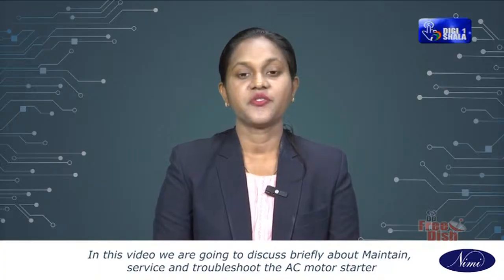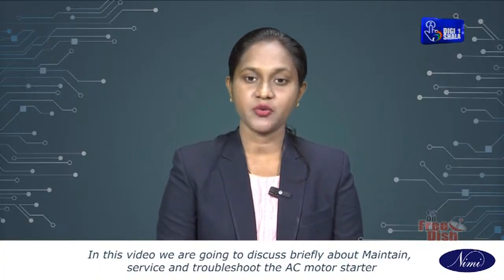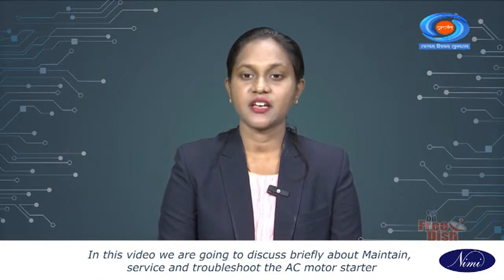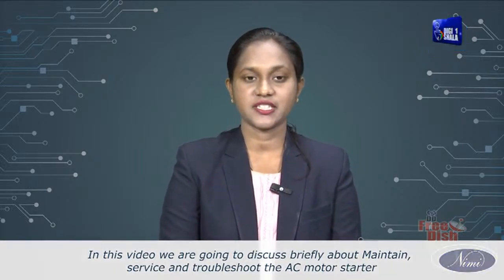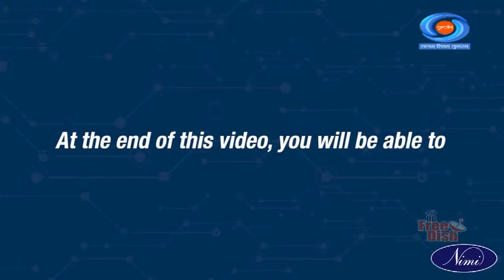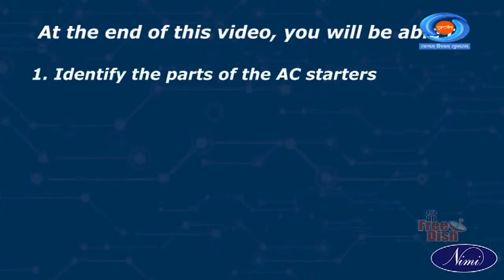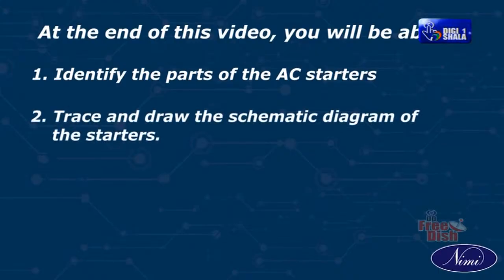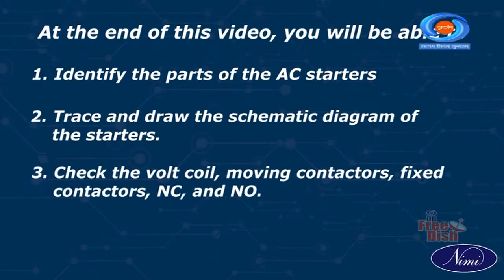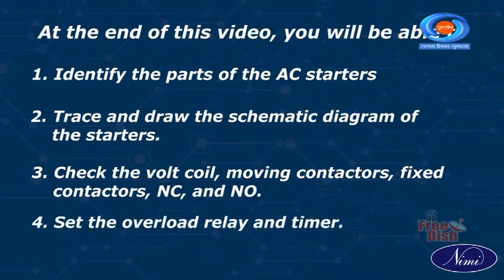In this video, we are going to discuss briefly how to maintain, service and troubleshoot the AC motor starter. Objectives. At the end of this video, you will be able to: 1. Identify the parts of the AC starters. 2. Trace and draw the schematic diagram of the starters. 3. Check the no volt coil, moving contacts, fixed contacts, NC and NO. 4. Set the overload relay and timer.